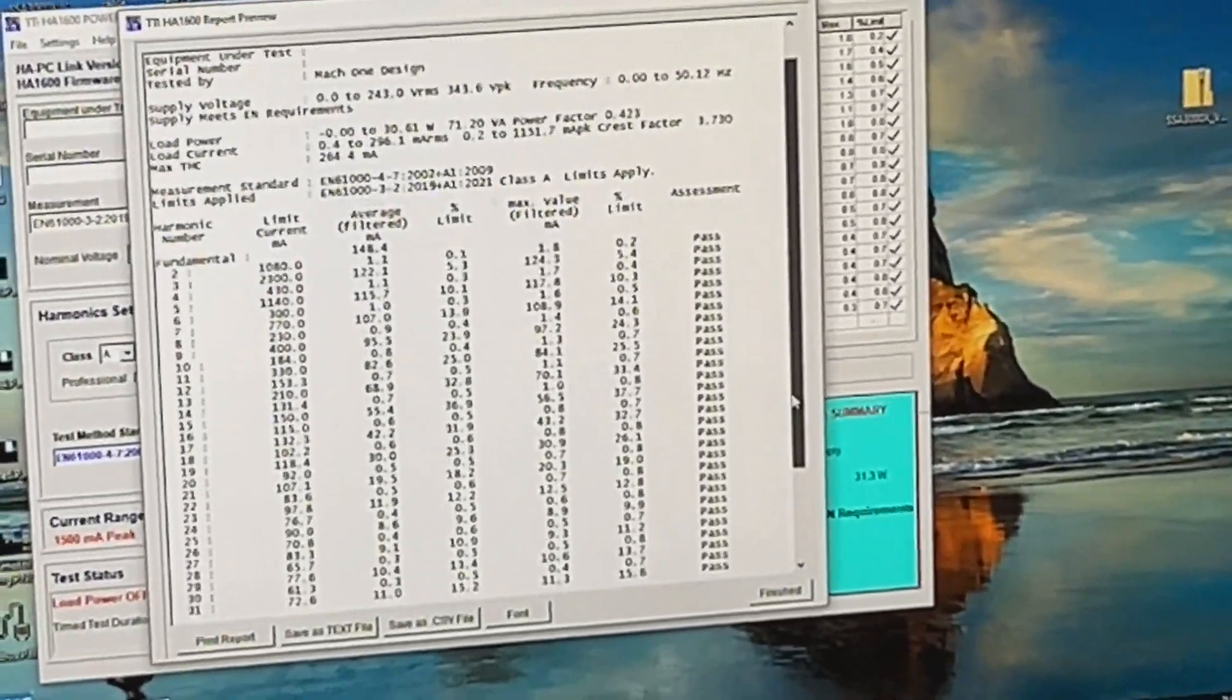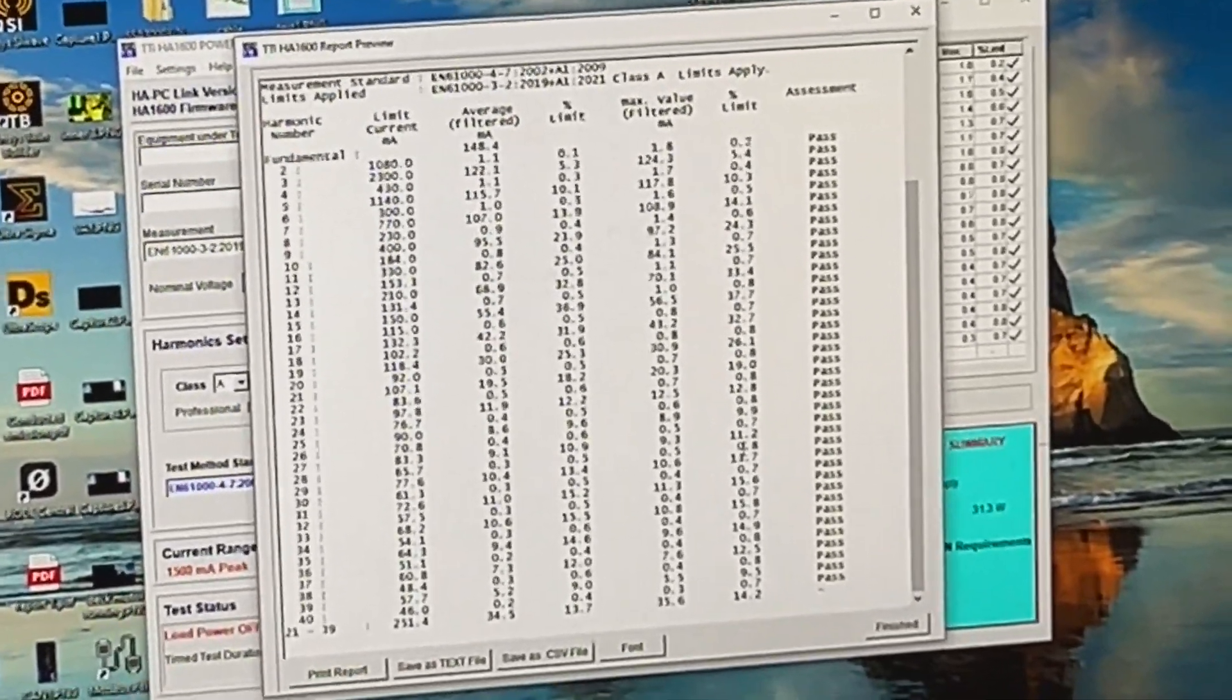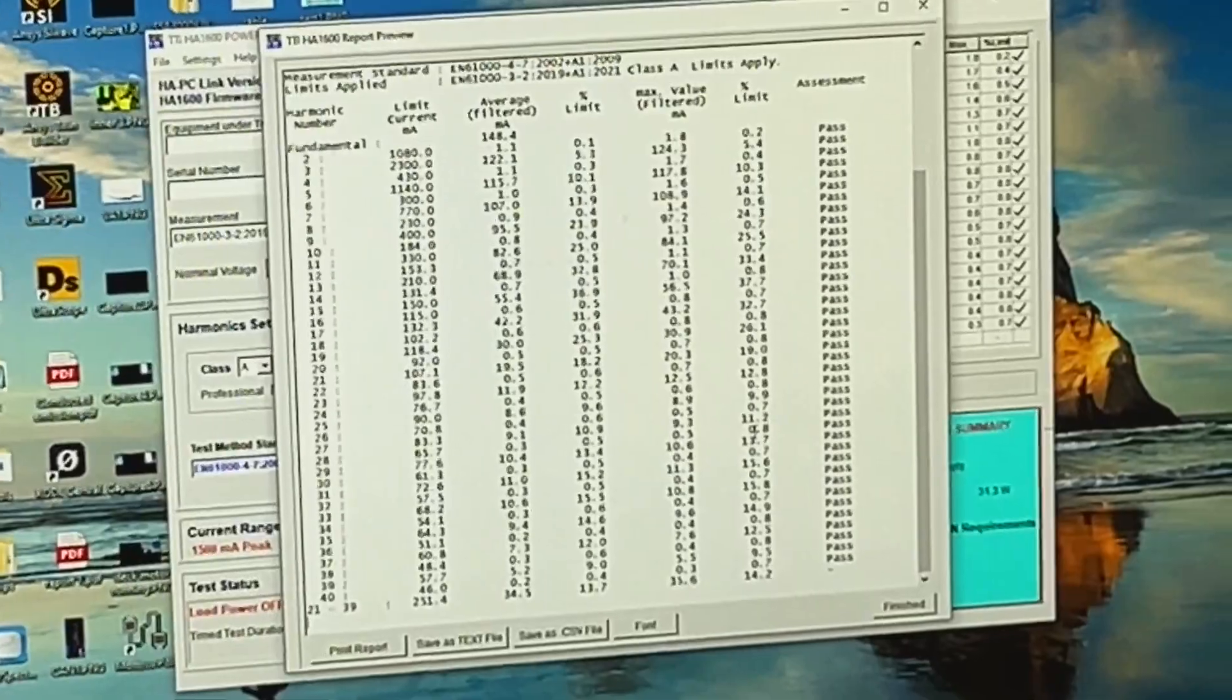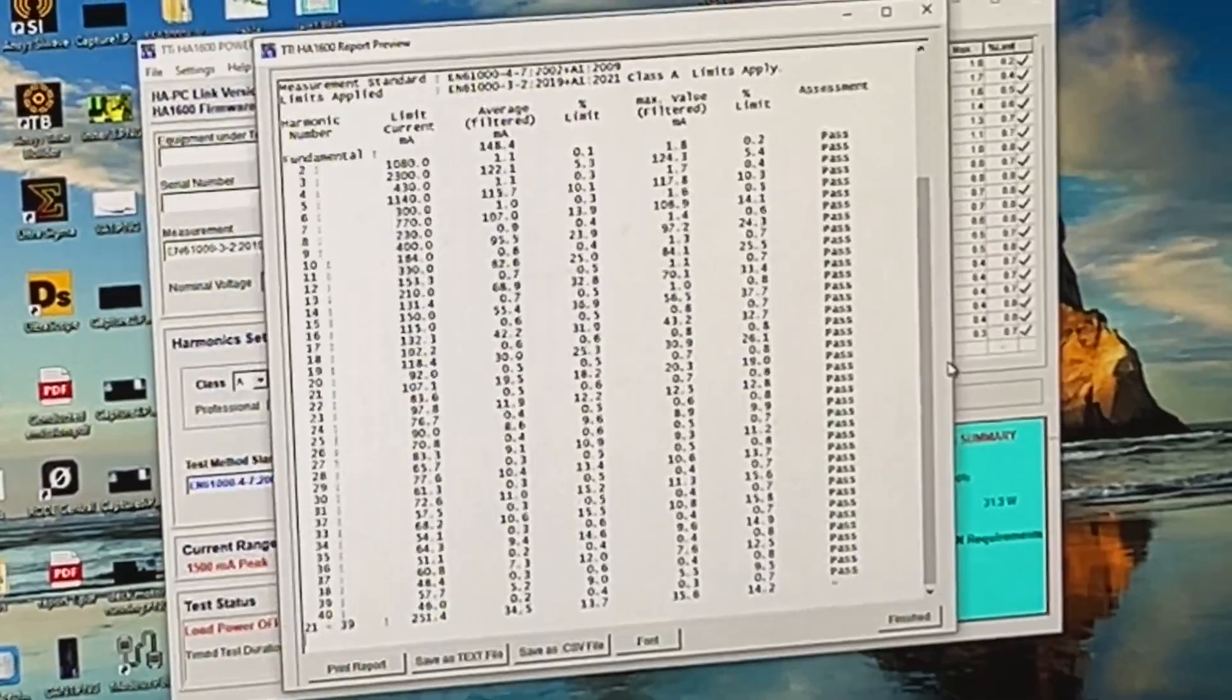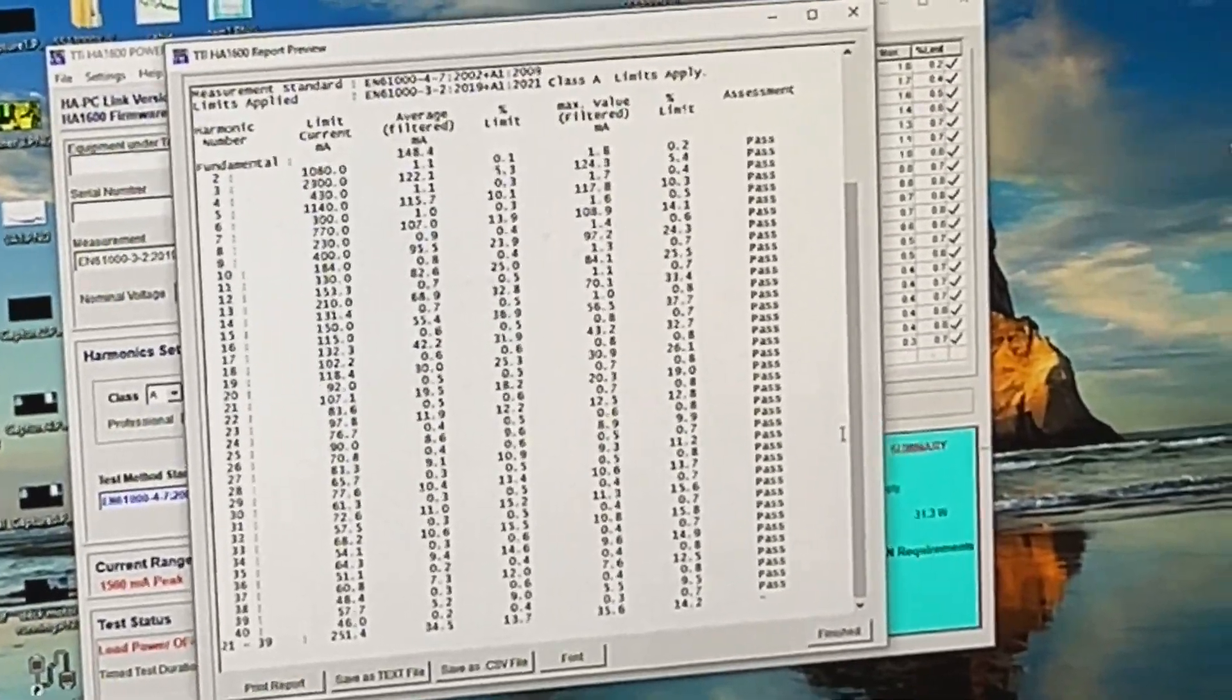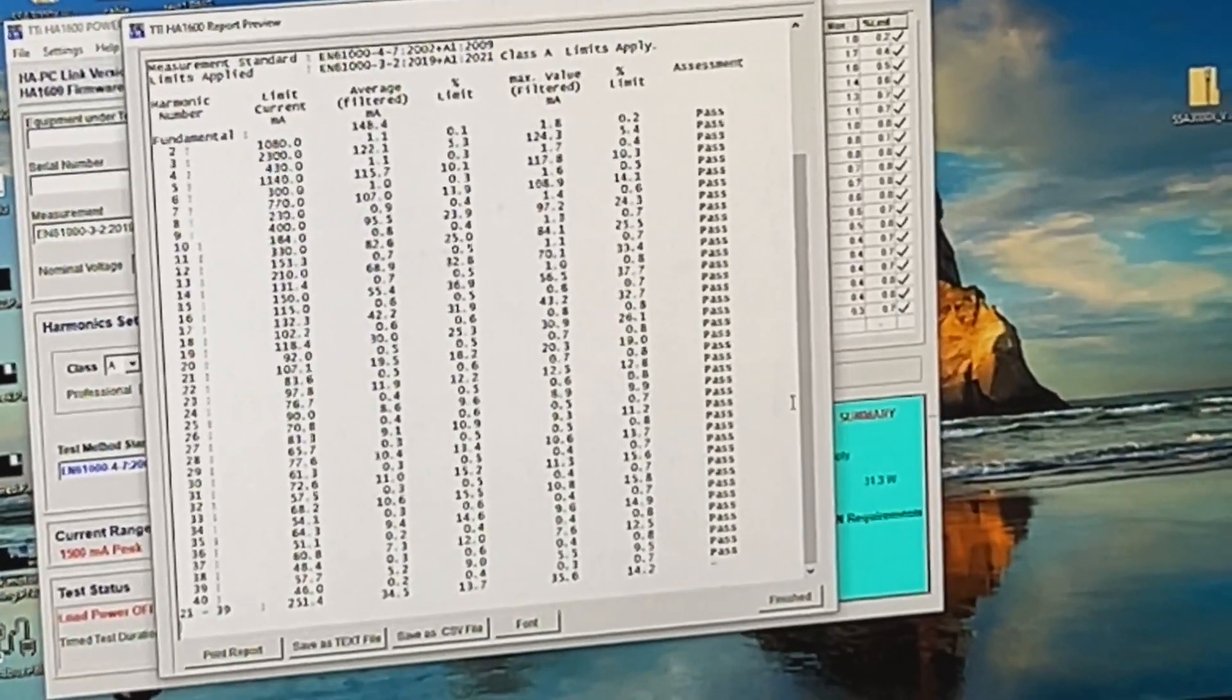So this is the report that generates. It tells you the voltage, current and all the harmonics content whether they pass or fail using whatever the standard defines. Because if you read the standard actually it's not simple, meets the limits or above the limits, because if you have a certain harmonics above limits you can still pass if you do the other calculation. So this software basically enables you to do that automatically rather than you have to calculate manually.